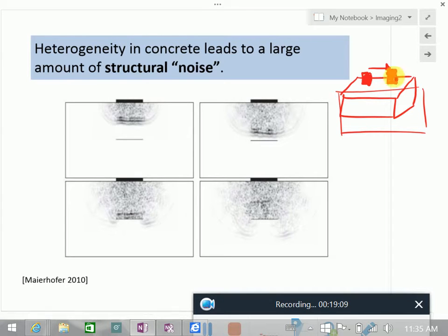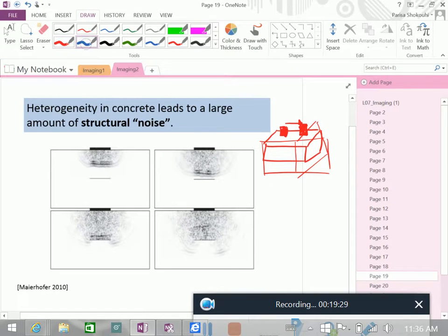And if I cut it in the other direction, we can call it B scan. And C scan is a plan view, but not plan from the top, but inside the material, when you slice it horizontally.